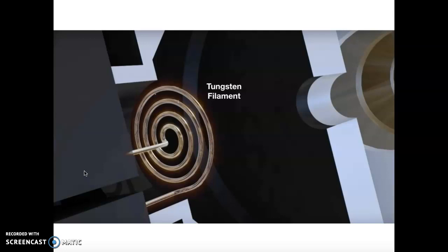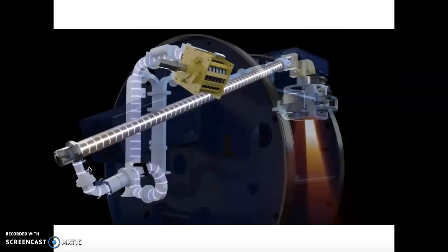And the electrons are then sped down this waveguide, this long hollow tube, because of the magnetron. The magnetron is here to produce radio waves, and it sends the radio waves down this pipe, and it comes up and hits the electron gun, and then it shoots these electrons down the waveguide at almost the speed of light.